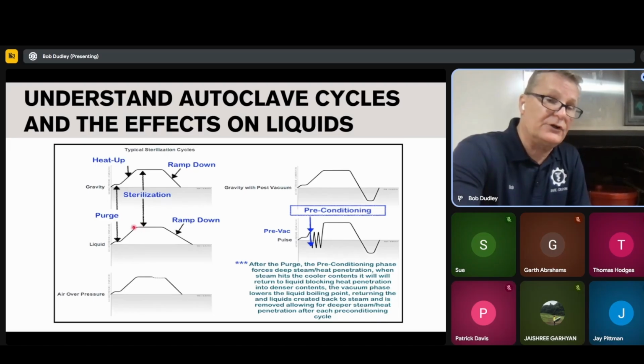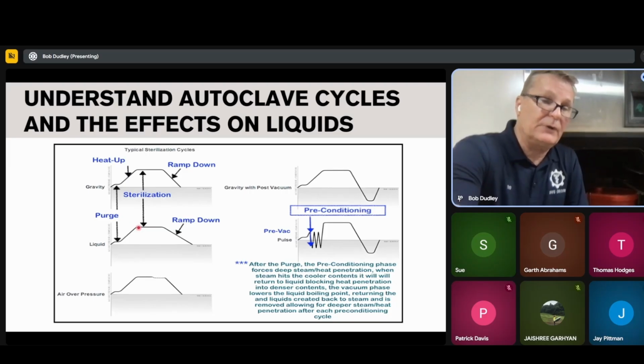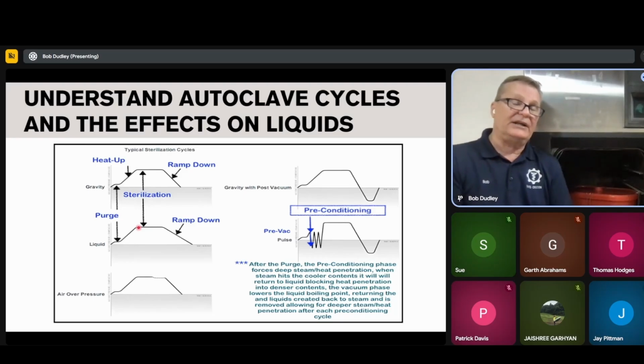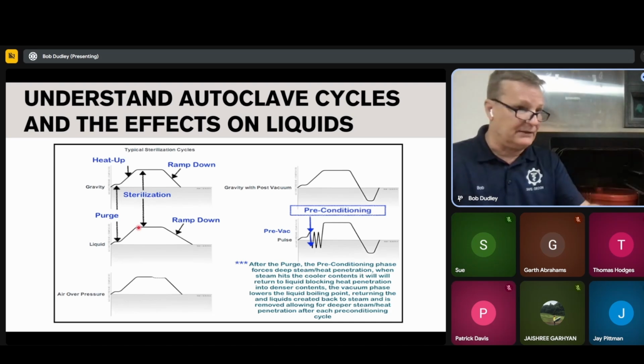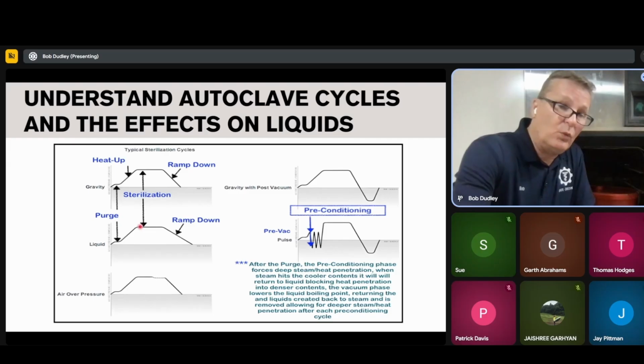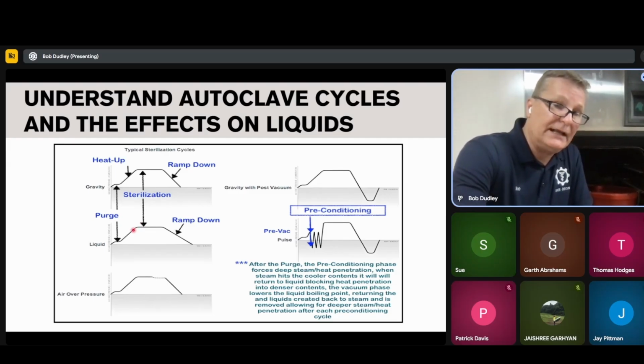And this is generally where you're going to get a lot of your failures for those that just love their autoclave. Generally, what happens is it's going to make its final check, and then it's going to look for drop rate, pressure, temperatures, jacket, chamber, and it goes through a lot of checks.